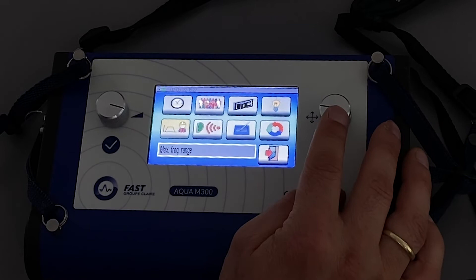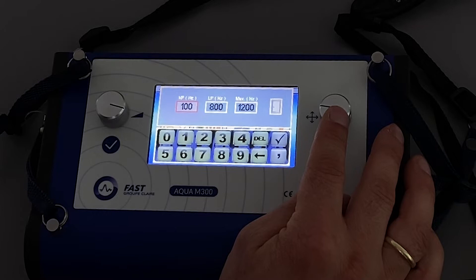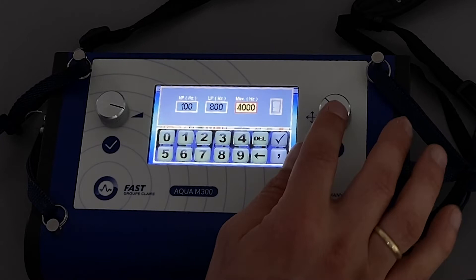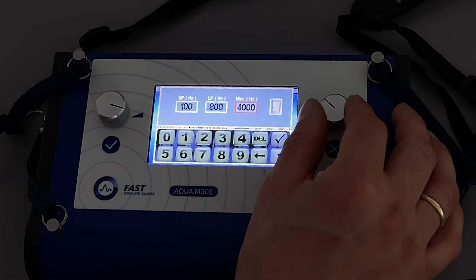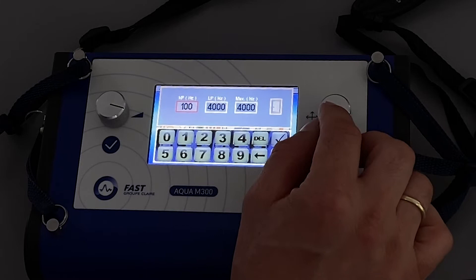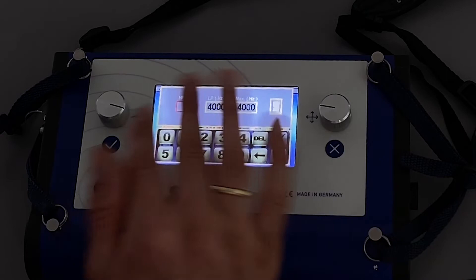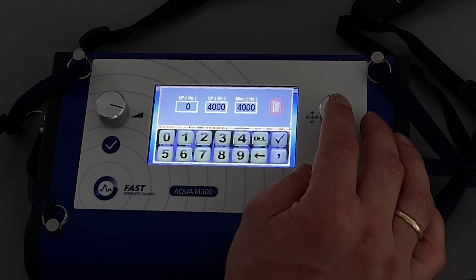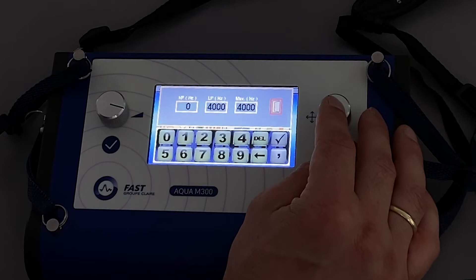The fifth icon is the frequency settings in manual filter mode. You can select up to 4000 Hz maximum frequency — a very broad bandwidth. You can also select preset filters; here the low-pass filters. I always like to hear all frequencies on the measurement position, so I select between 0 and 4000 Hz — completely open filters. Anything you change here will appear in the manual filter settings in the corresponding acoustic modes.